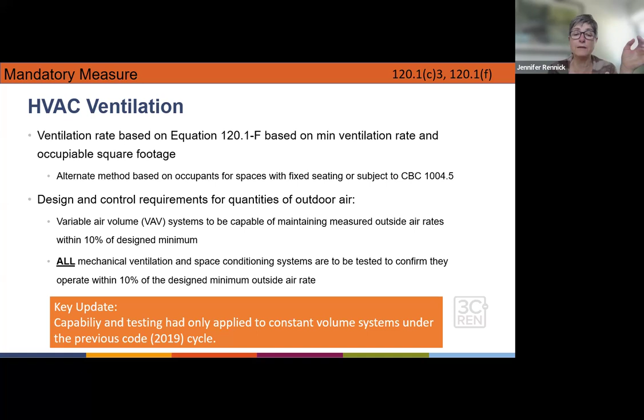What is different is that now we're going to have testing - specifically, we're going to test variable air volume systems to confirm they're capable of maintaining measured outside air rates within 10% of the design minimum. All mechanical ventilation and space conditioning systems are tested and confirmed to operate within 10% of the designed minimum outside air rate. This is new from the last code cycle, so maybe those of you in practice have seen this a bit.